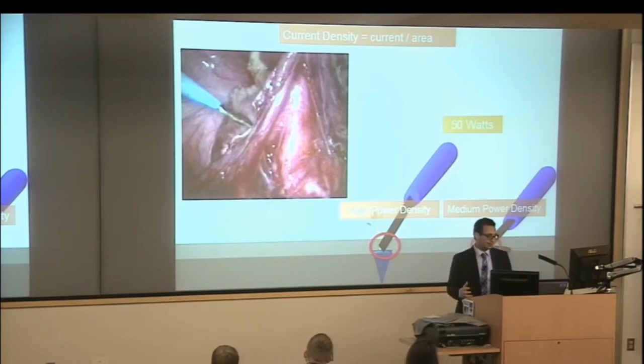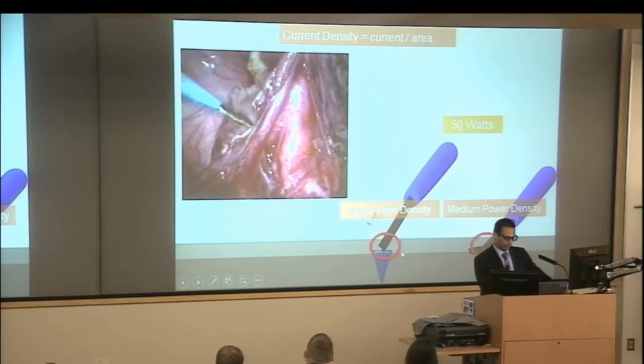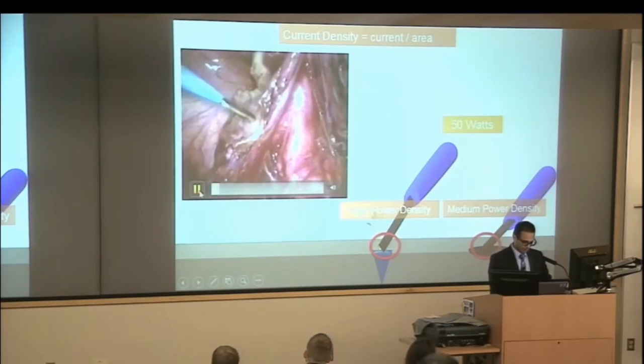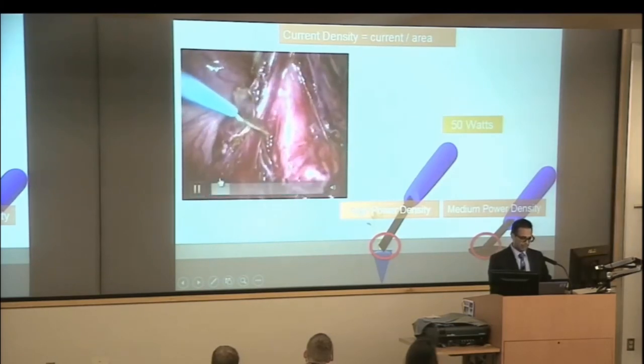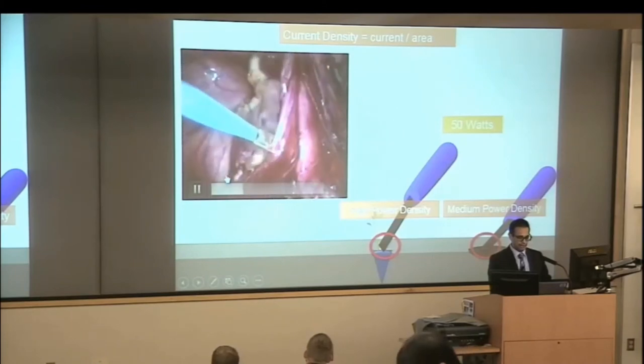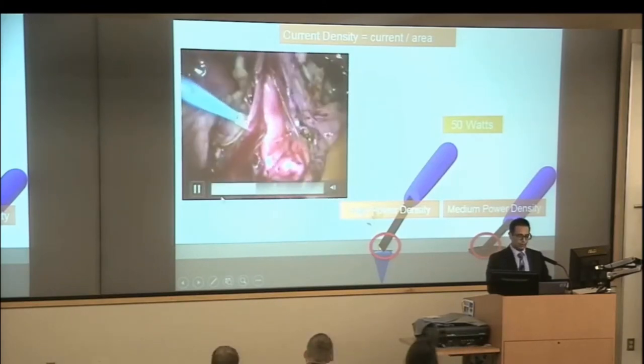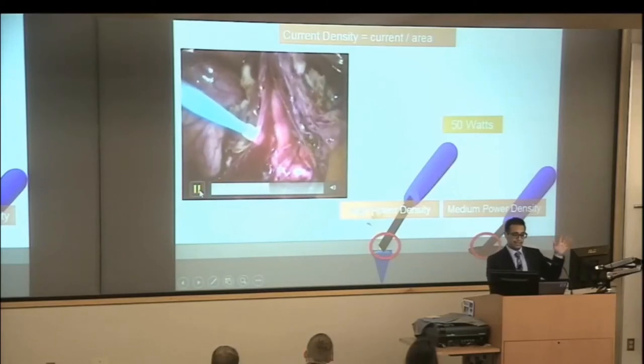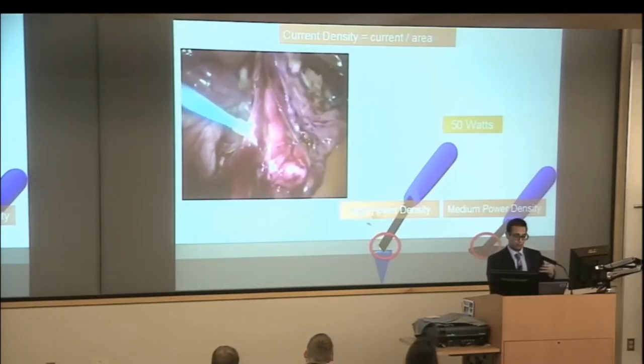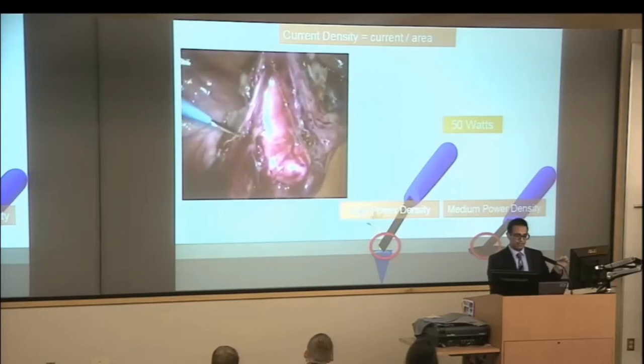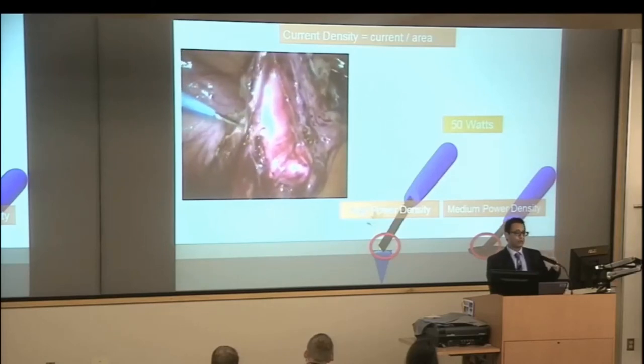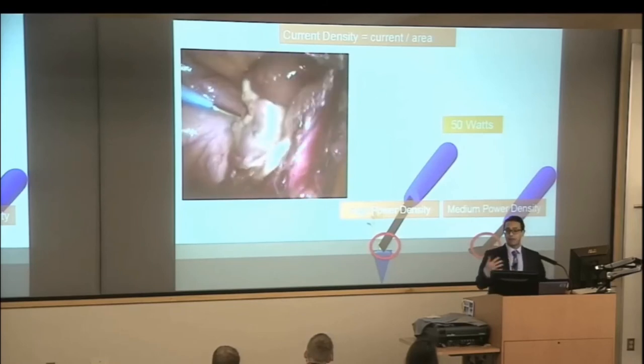This can be demonstrated with this monopolar device. You can use the tip or the flat part. The flat part gives you lower density and so a lower thermal effect, as shown in this video. Using the flat part over a larger surface area only raises the temperature to that 60-90 degree zone, enough to desiccate it, more for hemostasis. Whereas using the tip, it's more concentrated, so you get more thermal effect above 100 degrees Celsius, and more of a cutting effect.